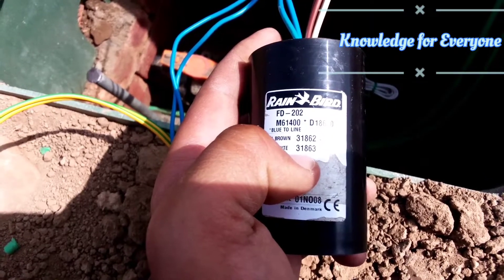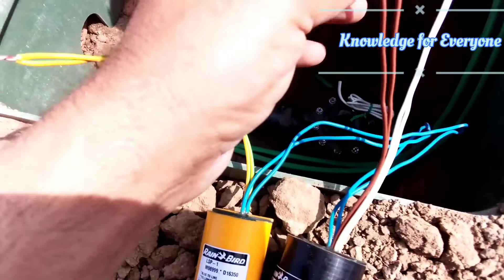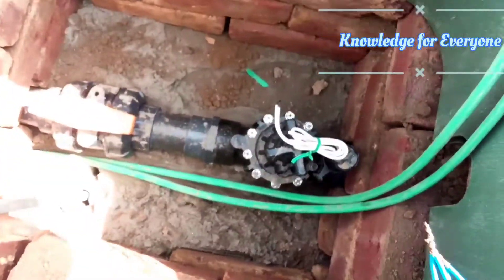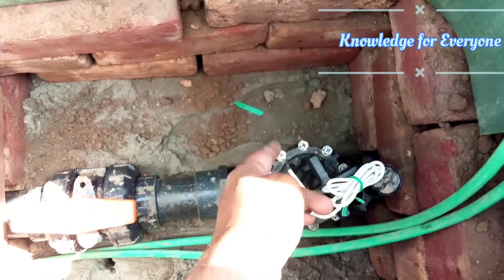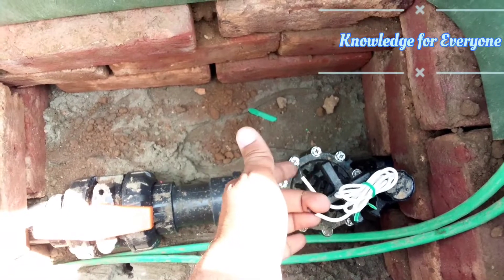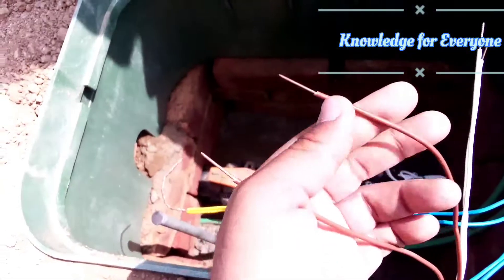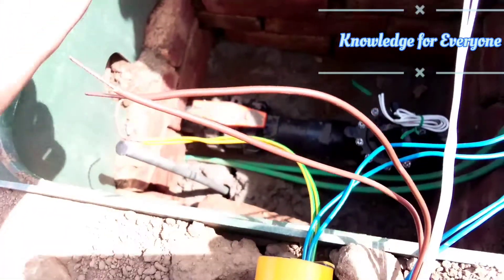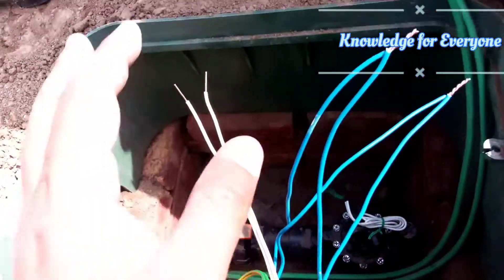We will connect the brown wires to the solenoid valve — let's suppose I have a solenoid valve here which is PGB 200. These are the two wires, so one wire will be connected to one terminal and one wire to the other. It doesn't matter if you exchange the wires, it doesn't matter which brown goes where. For the blue wires, you have to connect one to the live and one to the negative and positive.